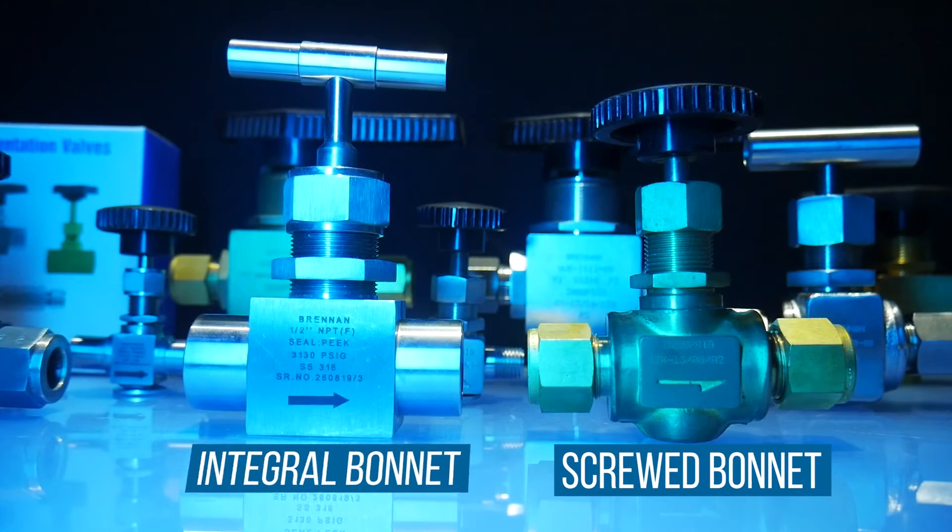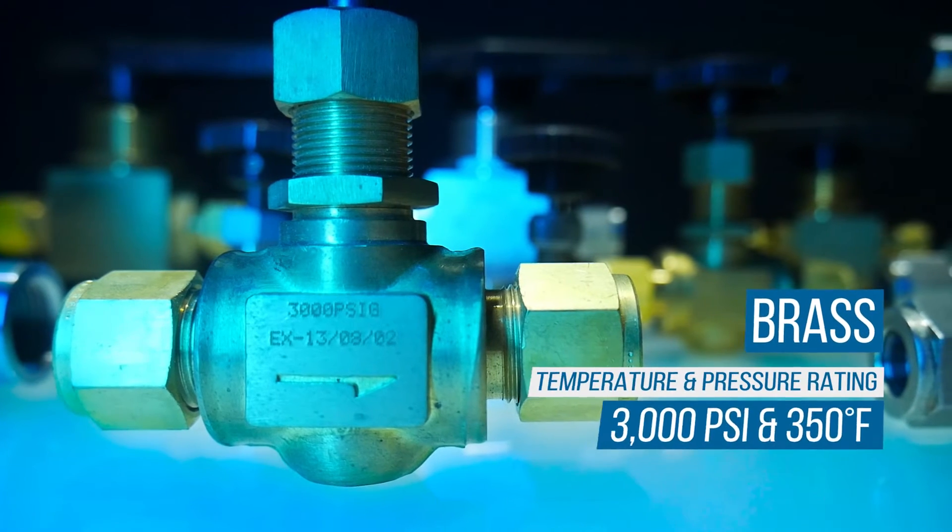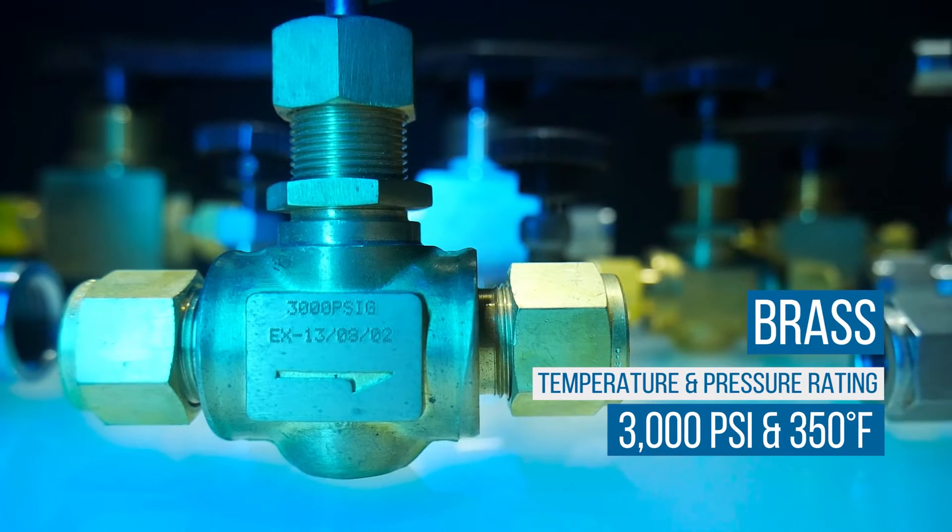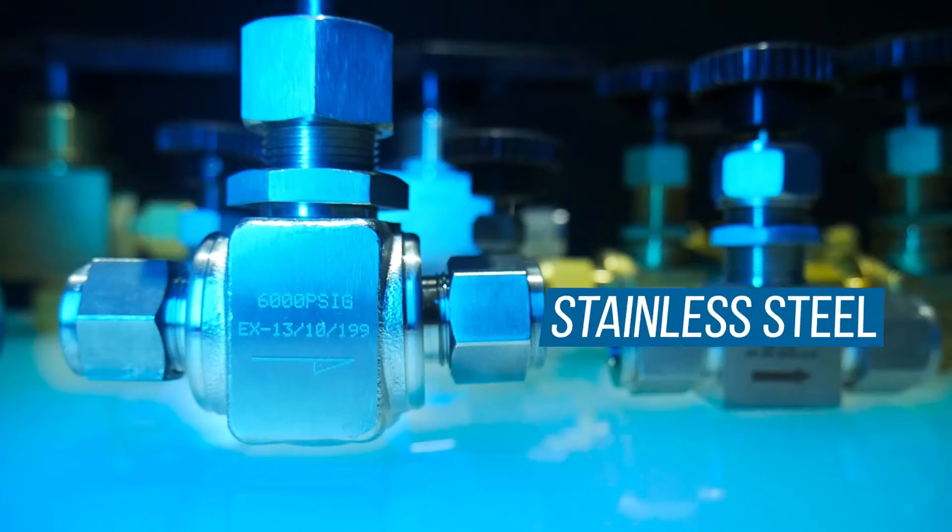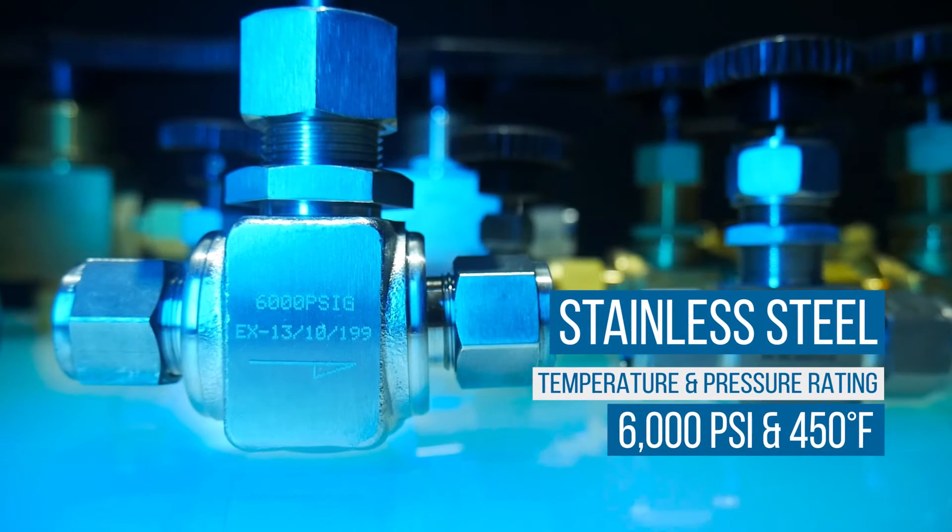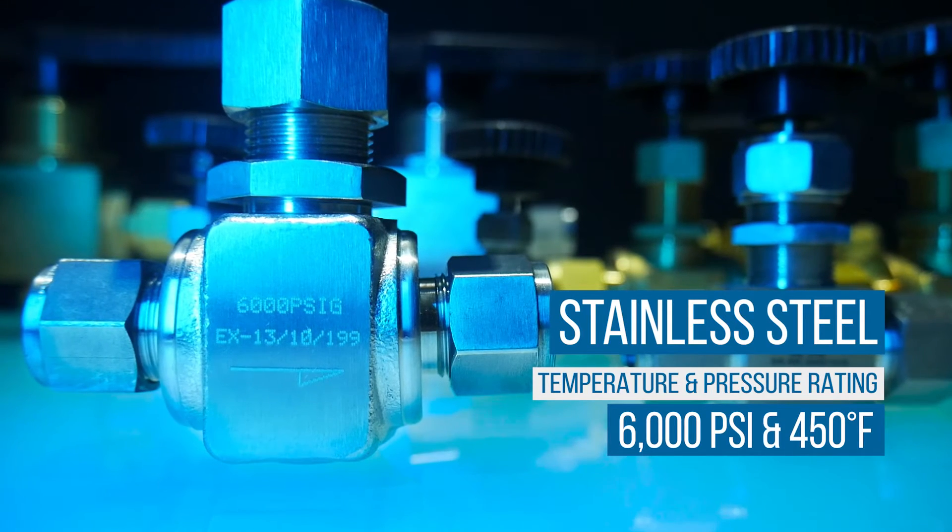Instrumentation needle valves are available with screwed bonnet or integral bonnet. Brass instrumentation needle valves are rated for pressures up to 3,000 psi and temperatures to 350 degrees Fahrenheit, while stainless steel instrumentation needle valves are rated for pressures up to 6,000 psi and 450 degrees Fahrenheit.